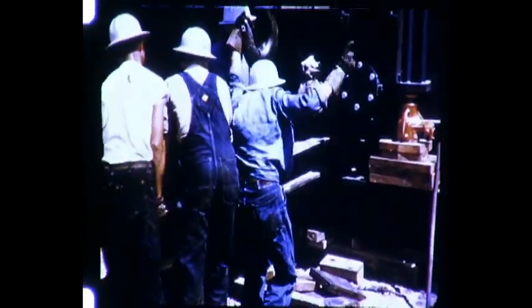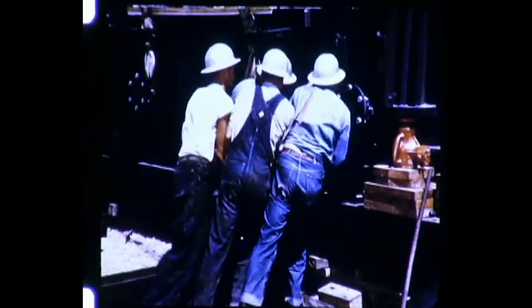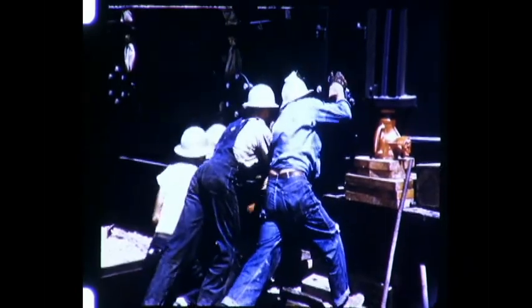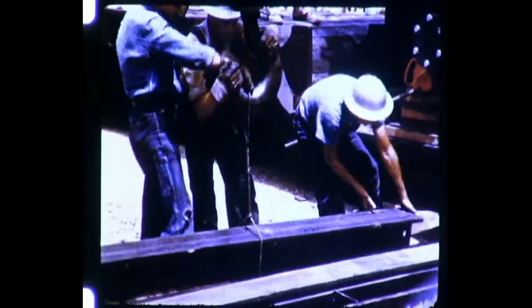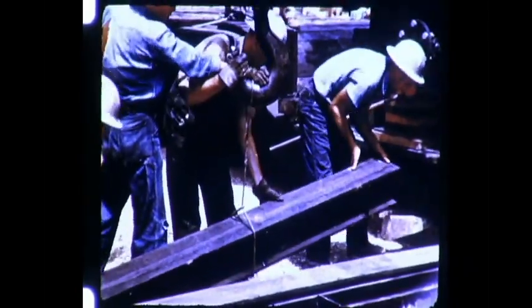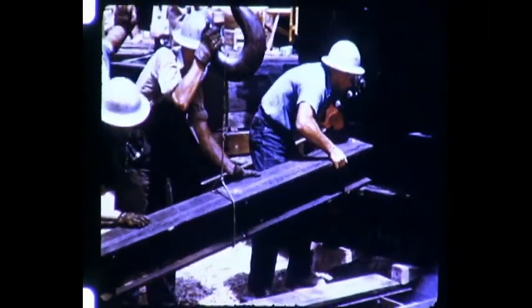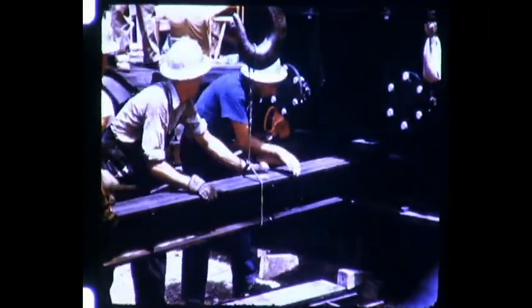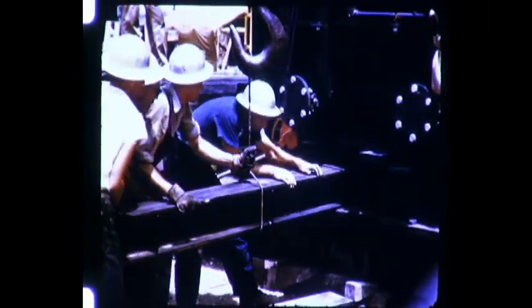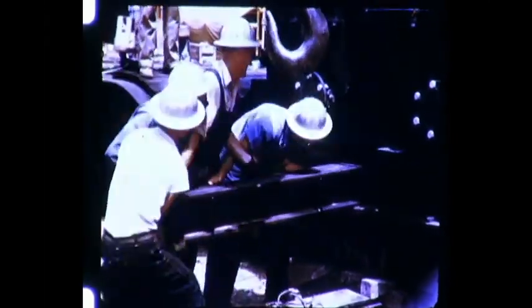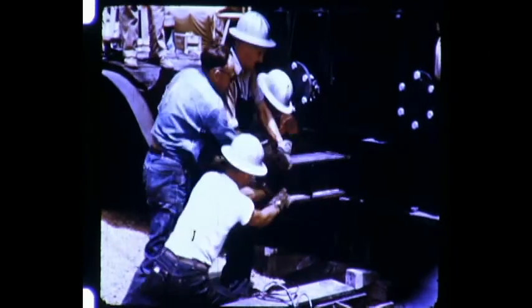Height of the unit is more than 10 inches now, and we're ready to bring in some small steel I-beams. The placing of the beams under the transformer preserves the gain in height and frees the blocking for further use under the jacks and base. With the beams in place, the crew can go ahead and raise the unit the last 6 inches needed to obtain a level above that of the footings.